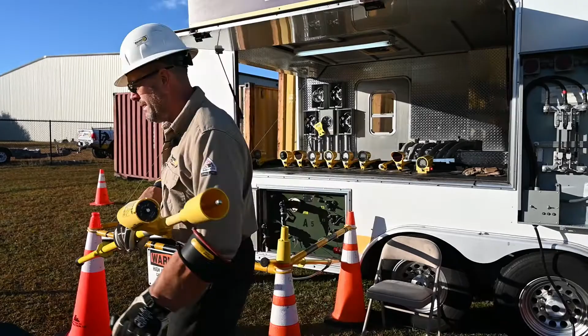Okay, so now we verify that the tool is accurate. We have a lack of all 3 voltage types, so we can place our TPGs now and set up our EPZ properly and safely. Five steps: we're going to test, open, test the tester, put on your grounds.